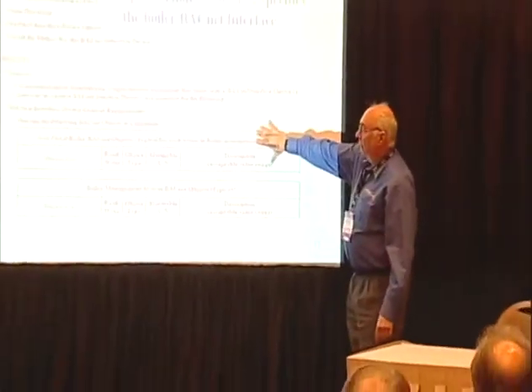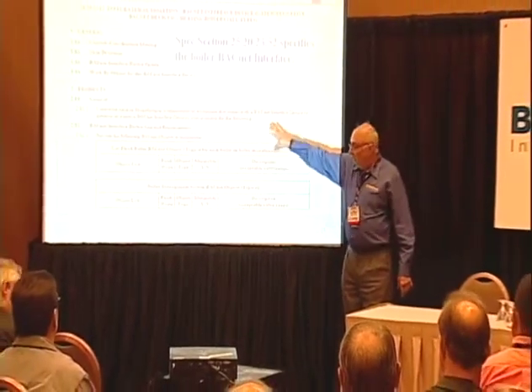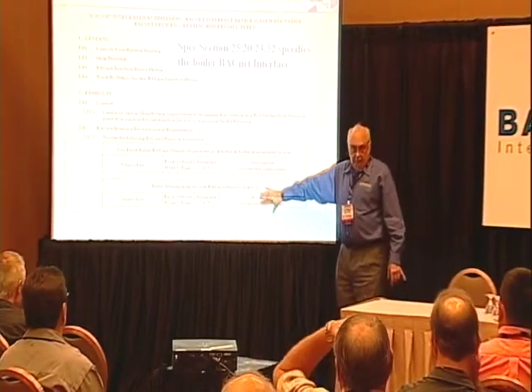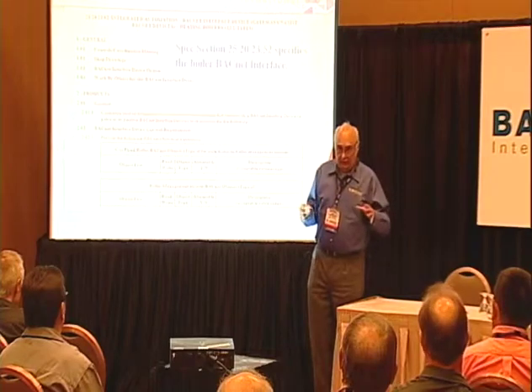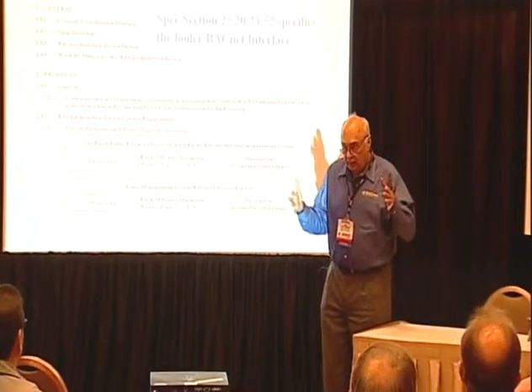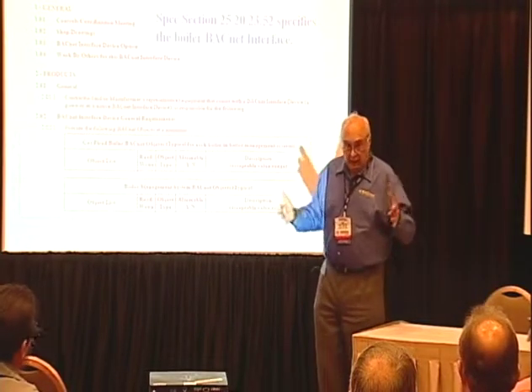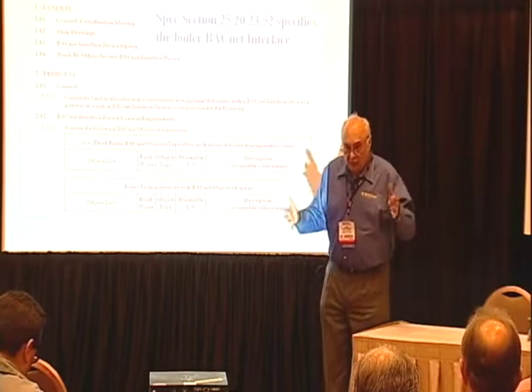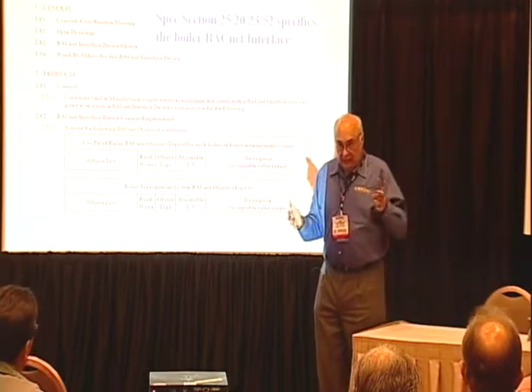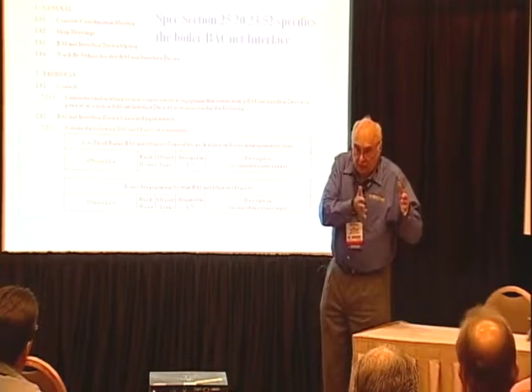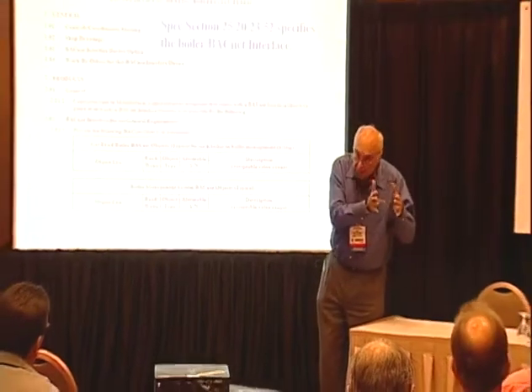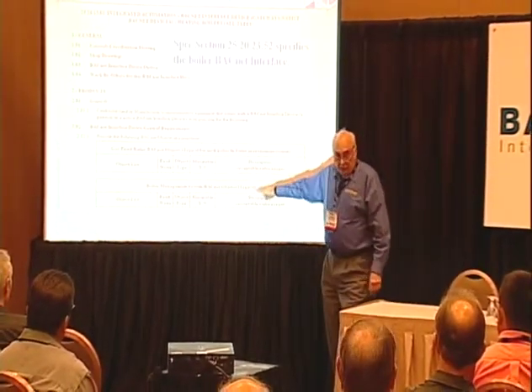Okay, so here's an abbreviated list of how our spec works. So we've got the boiler in 2352. So in 2520, 2352, we give the list of boiler objects that we expect to see and what the boiler management system is expected to do. Okay? Often with condensing boilers, for those of you who design systems, it's not unusual to have 3 or 4 condensing boilers to allow for staging of loads, right? The consultant designs the job for a design day, the coldest day of the year, but that's 2-3% of the time. Generally, you want to have it both for boilers and chillers. You want to be able to stage on your load as you need it and stage off your load when you don't need it. So there's a boiler manager, a traffic cop that says, okay, you run, oh, you're in fault, okay, it's your turn to run.